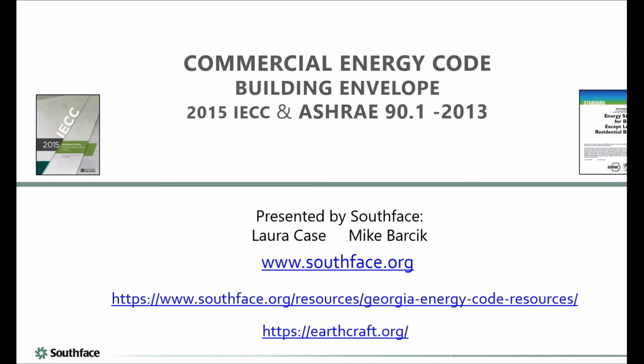And I should mention that it's now January of 2020 as we record this. Georgia is on to its latest energy code. The 2020 Georgia Energy Code is actually based on the IECC 2015. And whenever you adopt the IECC, you inherently also get an ASHRAE 90.1, and the version of 90.1 is 2013. So really, in Georgia, you can use either commercial energy code.